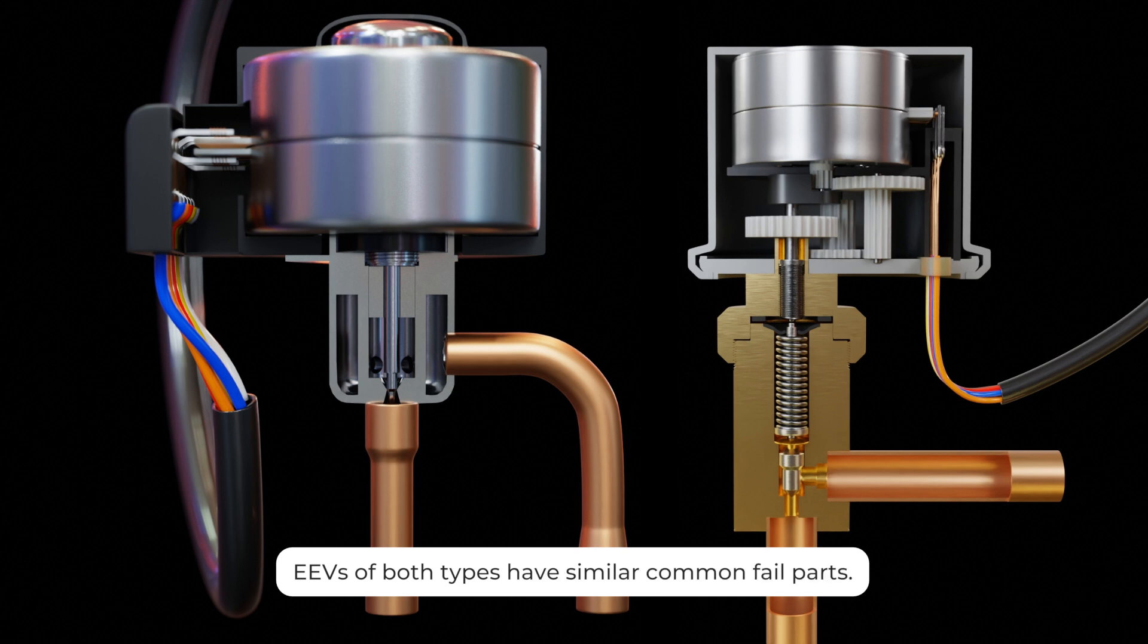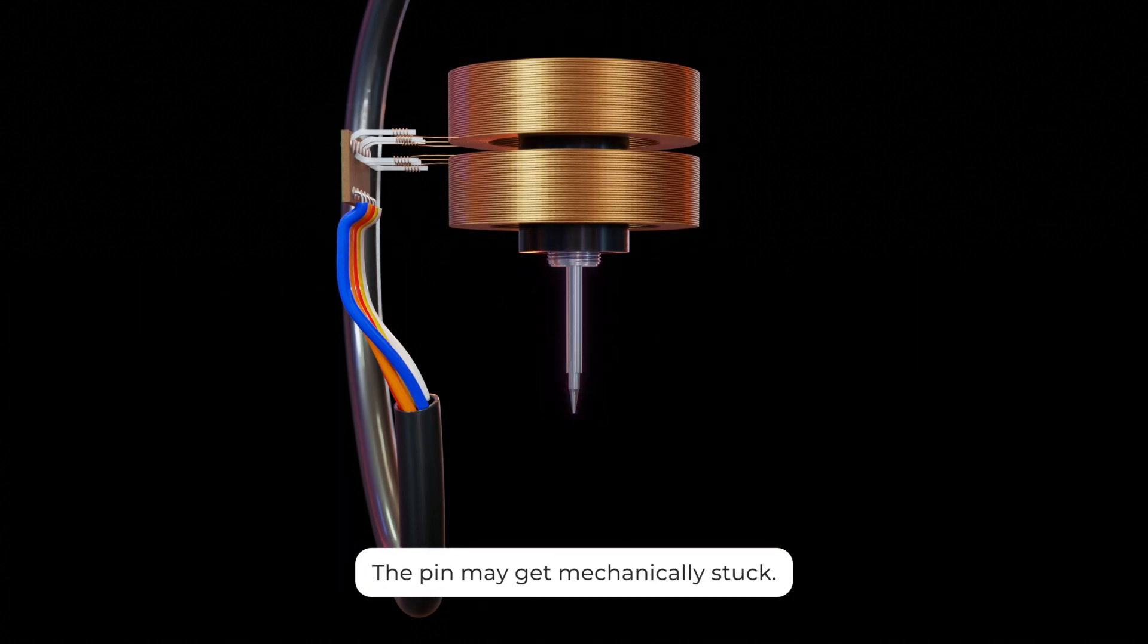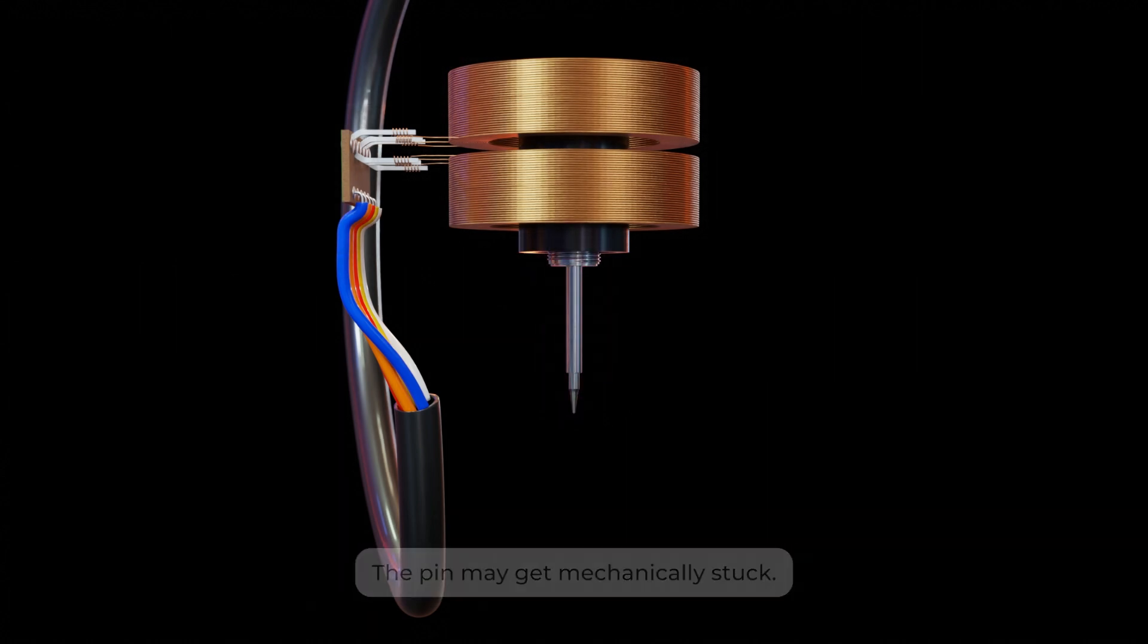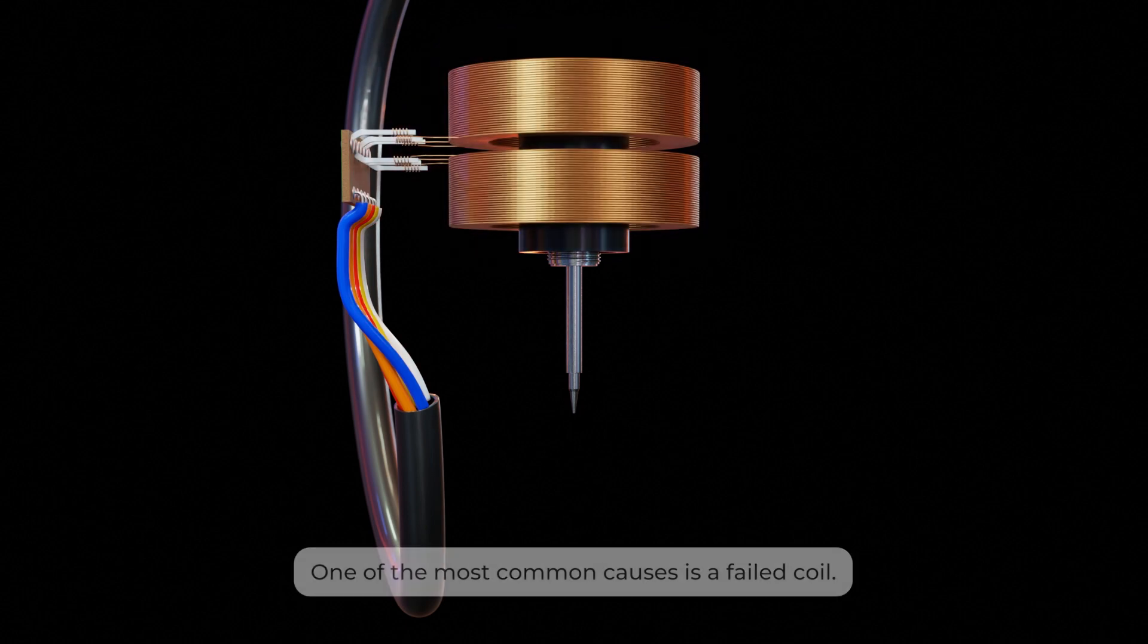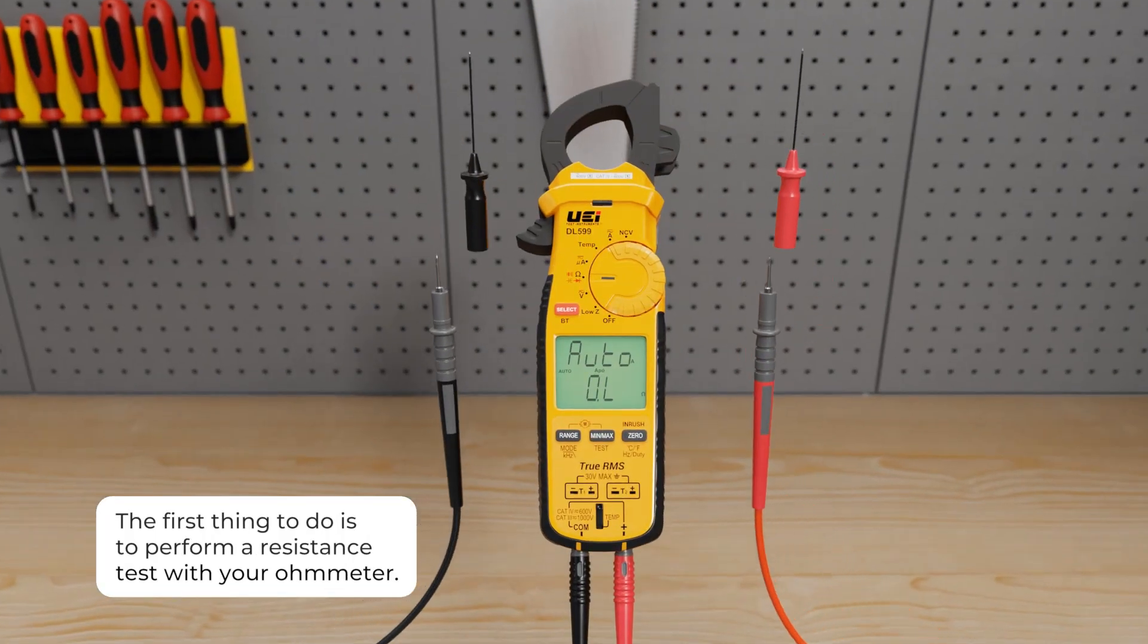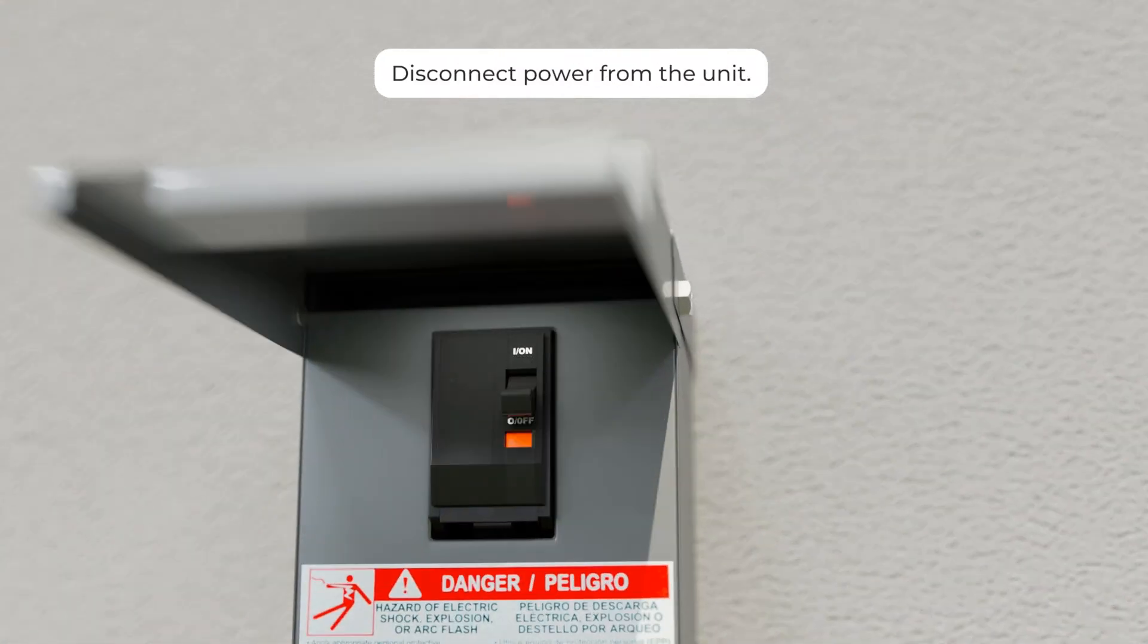EEVs of both types have similar common fail points. As with mechanical metering devices like TXVs, the pin may get mechanically stuck. One of the most common failures is a failed coil. The first thing to do is to perform a resistance test with your ohmmeter. But first make sure you disconnect power from the unit.